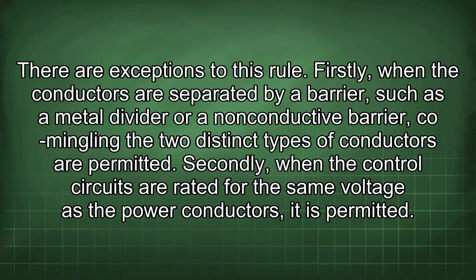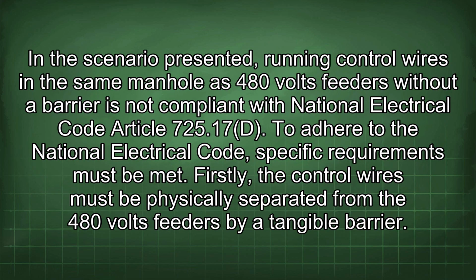Firstly, when the conductors are separated by a barrier, such as a metal divider or a non-conductive barrier, commingling the two distinct types of conductors is permitted. Secondly, when the control circuits are rated for the same voltage as the power conductors, it is permitted. In the scenario presented, running control wires in the same manhole as 480 volts feeders without a barrier is not compliant with National Electrical Code Article 725.17(D). To adhere to the National Electrical Code, specific requirements must be met.